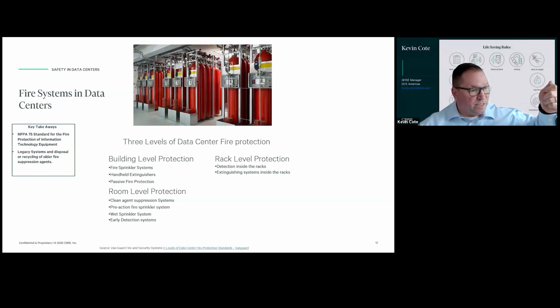Usually 2 smoke detectors would have to go off, or if you have rack level protection, which is the 3rd level, 2 racks go off, then that major system would activate. Inside the racks, there could be fire suppression, and you'll usually see detection inside the racks too, monitoring temperature mostly, making sure it doesn't exceed or keep climbing.